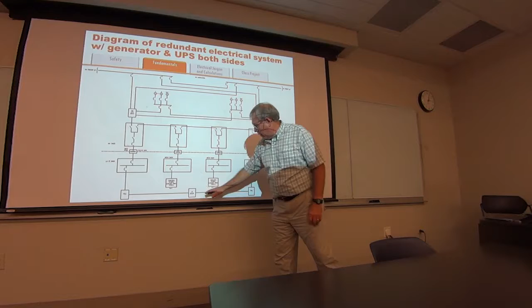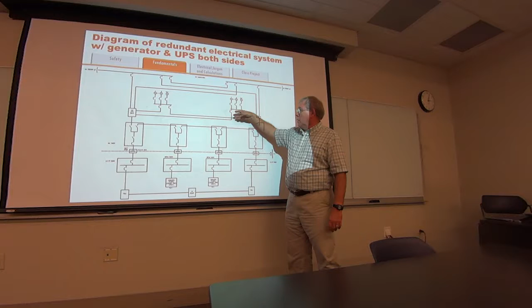That's what I think. Now this is a different approach. Here's your power, IT stuff, chillers, switchboards. This is medium voltage switchgear, they call it source transfer, and it can find voltage on either side. If this side goes down, this switch will close these switches and feed everybody from this way. You got generators up here if you lose everything.